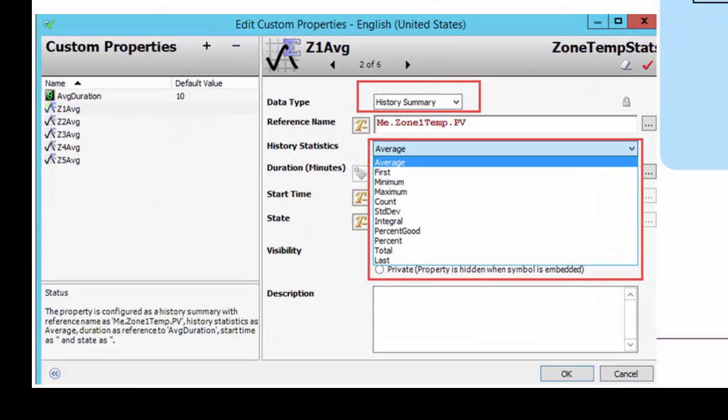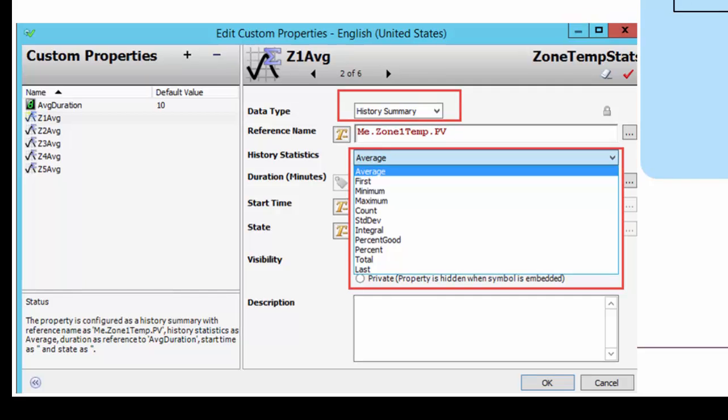First, we're going to take the concept of custom properties to retrieve the average zone temperatures over a configurable time period. One of the interesting things about custom properties in ArchestrA Graphics is a data type called History Summary. That gives you access to different types of statistics you can query from the Wonderware Historian — such as average, min, max, standard deviation, and so on. We're going to be using average in this case.